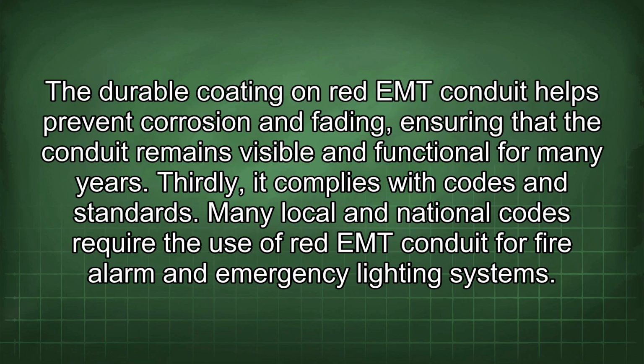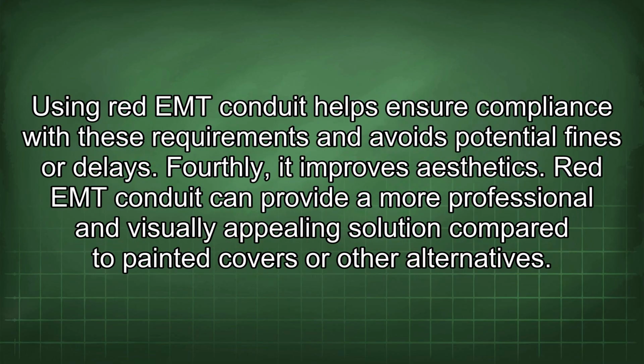The durable coating on red EMT conduit helps prevent corrosion and fading, ensuring that the conduit remains visible and functional for many years. Thirdly, it complies with codes and standards. Many local and national codes require the use of red EMT conduit for fire alarm and emergency lighting systems. Using red EMT conduit helps ensure compliance with these requirements and avoids potential fines or delays.